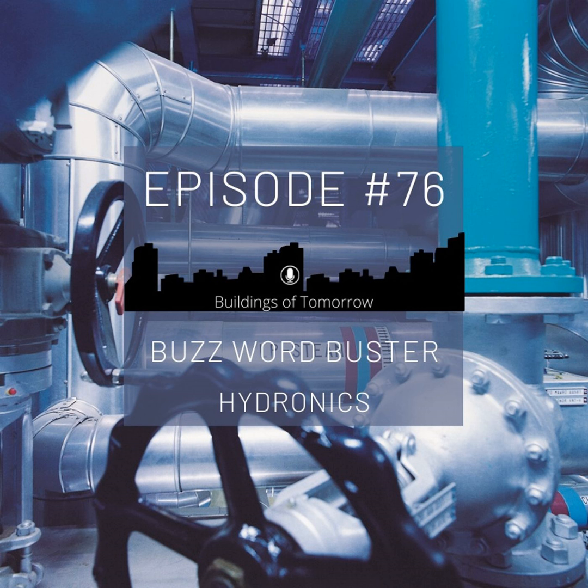Okay, beautiful. And related to that to a certain extent, the delta P V100? Yes. As you said, it's related because it also says V100. So it's the delta P, the pressure differential that we would like to have at this valve when we have the nominal flow derived from the power equation. And it's important that we consider that with the KVS valves in order to reach a good controllability of the system.